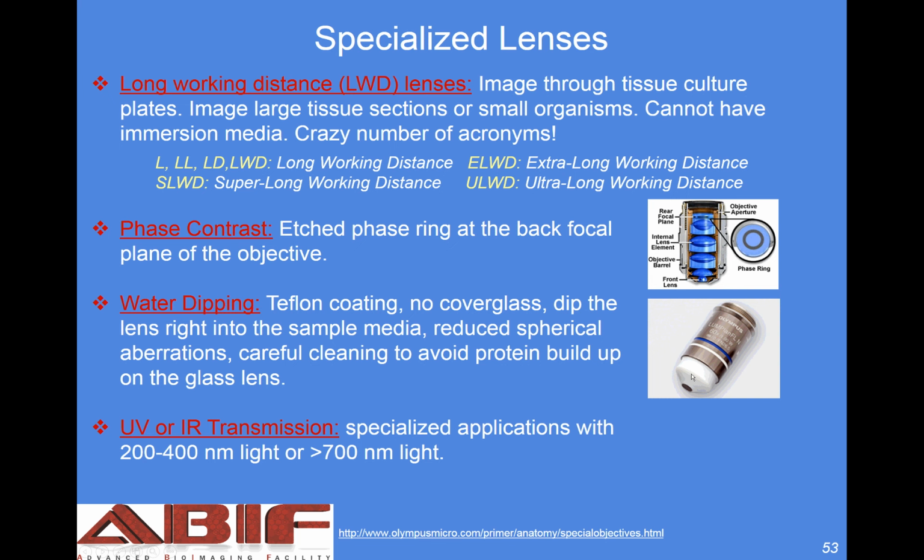They don't go through a cover glass, but the lens is dipped right into the media. So these are used on upright microscopes, typically with biological samples in an aqueous environment. The important thing with these is to carefully clean them to avoid buildup of salt and protein on the lenses after use. So they need to be rinsed really well with water after use.